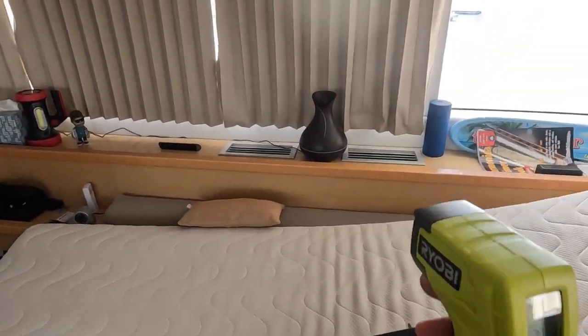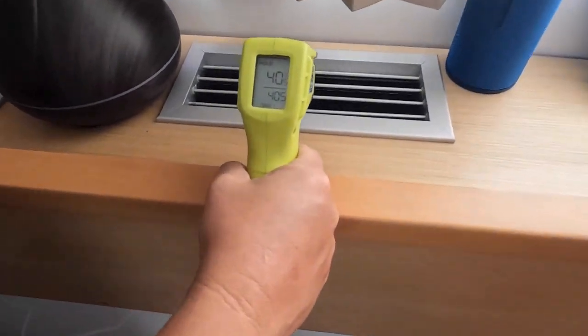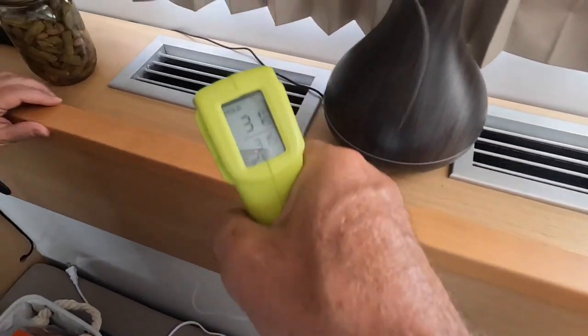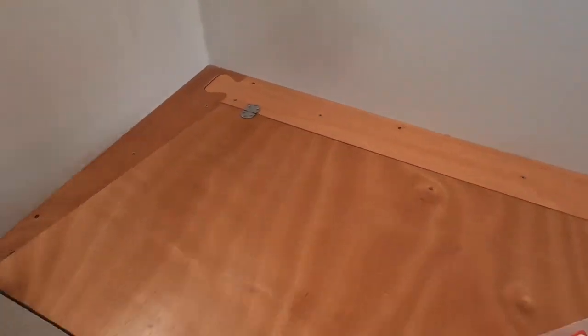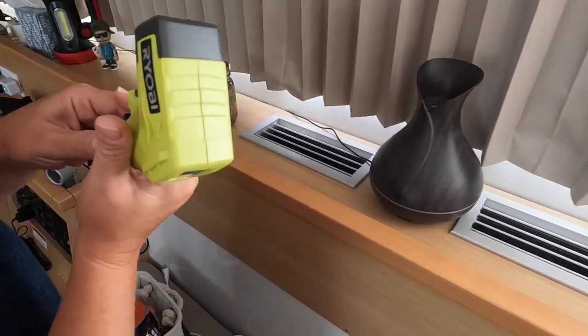We're going to run the barnacle buster through this second unit as well and hopefully get the temperature down on it. The other one was reading 58. If you can read that it says 57, that one says 40, 36. It's 42 now - it was reading 70, 70. So we ran the barnacle buster on it, had it hooked up for about almost an hour and a half, and it went from 70 down to about 40.